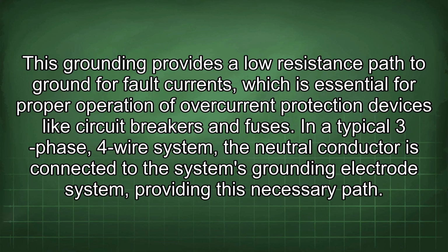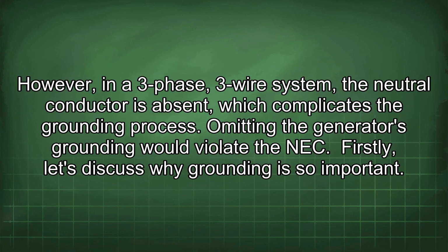In a typical three-phase, four-wire system, the neutral conductor is connected to the system's grounding electrode system, providing this necessary path. However, in a three-phase, three-wire system, the neutral conductor is absent, which complicates the grounding process. Omitting the generator's grounding would violate the NEC. Firstly, let's discuss why grounding is so important.